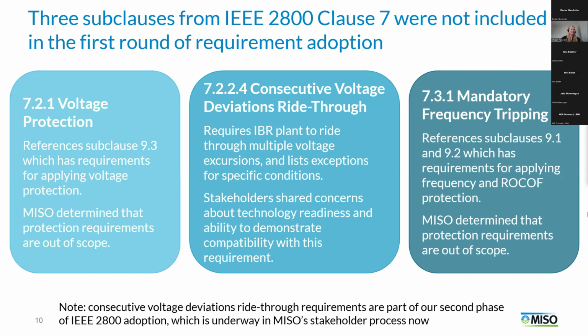Great, thanks. So we excluded subclauses 7.2.1 and 7.3.1 from our adoption because we determined that the protection items were kind of out of scope for MISO. Additionally, we did not adopt the consecutive voltage deviation ride-through requirements in this first phase. This decision was made based on stakeholder feedback that we received and information from OEMs that we gathered through outreach and through attending industry forums, saying that this was one of the more challenging requirements to fully understand and ensure inverter compatibility with. Just to note, though, we have actually included this in our second phase of 2800 adoption, which is underway now, as I mentioned, just because the second phase requirements will be adopted and effective later than this first round. And we've gotten some information from OEMs about when inverters that are compatible with this consecutive voltage deviation ride-through requirement will be available.